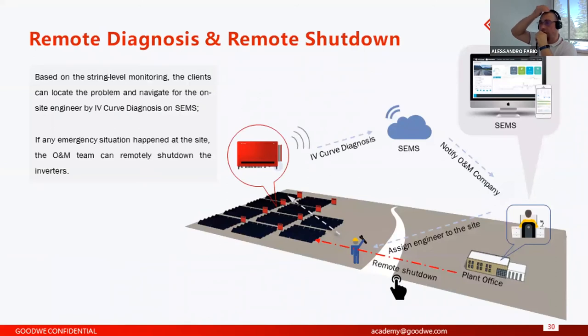Another possibility is the remote analysis and remote shutdown. Starting with the remote shutdown, it is a special feature integrated in all our inverters. It is the possibility to connect all inverters together. So we speak about 40 inverters together, and between the plant office, where there's a remote shutdown, and the PV plant, 1 kilometer, so more or less 1,000 meters, you can shut down completely the PV plant with only one button, for example, an emergency button.